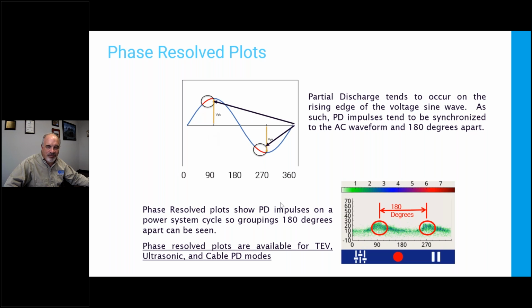energy. If I look at this phase resolve plot, each green dot is one event, and it shows the phase angle and the amplitude. I let that run over a few seconds. I've got a lot of dots, and I can see I've got two groupings of energy that are half a cycle apart, and that's an indication that whatever I'm looking at is synchronous with the power system and caused by the power system. And so that's going to give me a real indication that I'm not listening to a fan or a light or a freight train even. It's something caused by the power system. That's going to be a good indication that I've got PD.